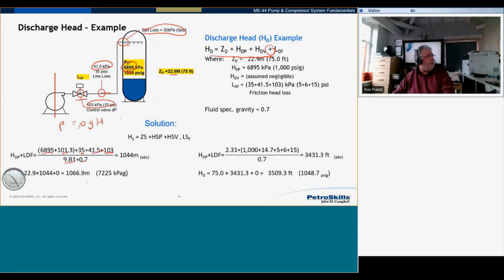I'm going to have to move my clock now, aren't I? I knew that was a bad idea. Okay. So what we've got now is the elevation, 22.9. We've got the total pressures, which are converted into head. And now we get 1,066.9, which comes out at 7,225 kPa G, if you want to go that way. But it's 1,066.9.